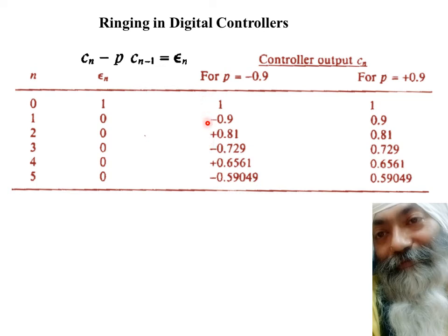So there is very fast and quick motion of control output, which is making the final control element move from almost fully open to fully closed to nearly fully open to nearly fully closed, and so on and so forth. So it's not possible for the final control element to follow this kind of instructions coming from the controller. It's very difficult, and we say that this controller is not suitable for most of the practical applications.